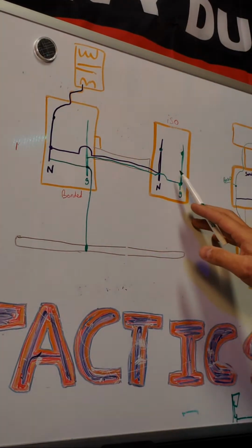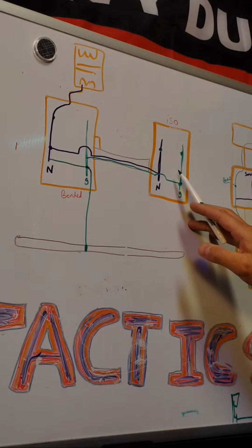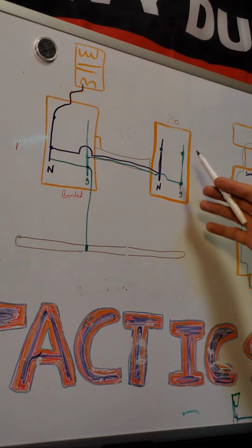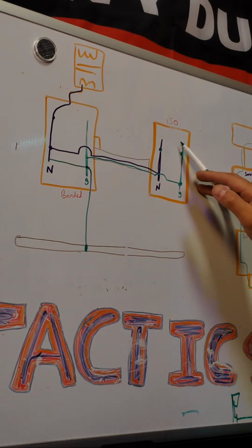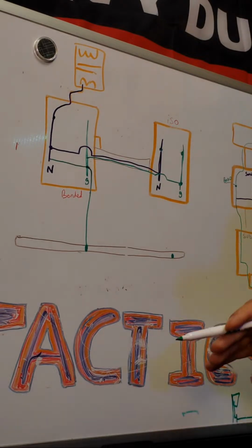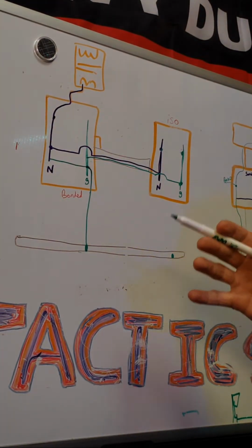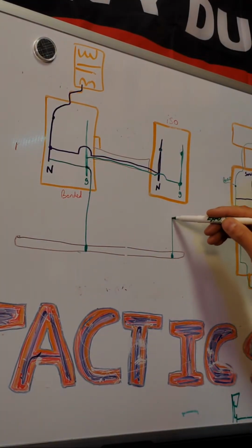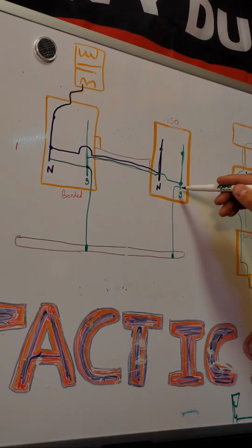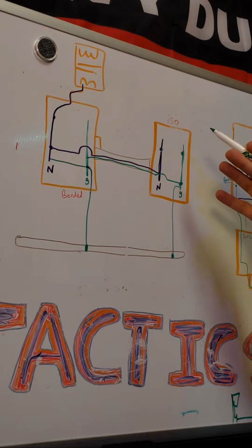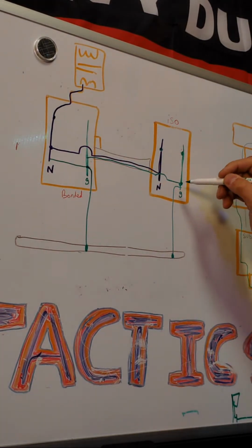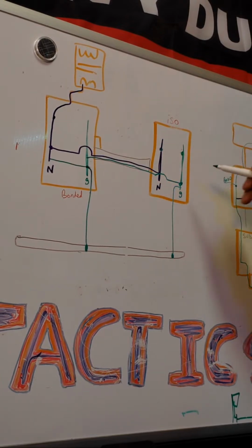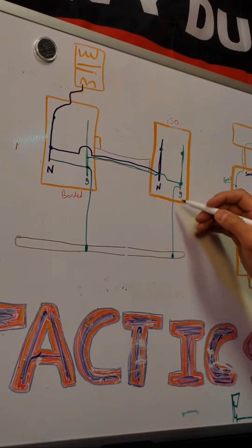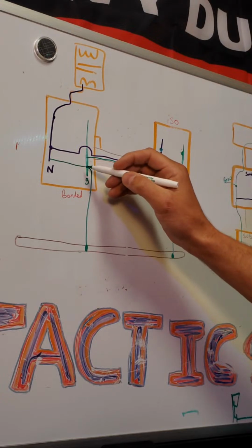So if this was an old sub panel in the closet and we happened to leave the old, right, because it used to be the service equipment, this is pretty common. So this panel here used to be the service panel, and it was in the closet. And we left that old number 6, which was no longer the proper size, but we thought to ourselves, hey, more grounding is better than less grounding. So we left it bonded. And we left that number 6 on this ground wire. We've unfortunately created a parallel path, and in the worst way too, because any current that was on the neutral is now going to be half on the ground, and we just introduced current to our pipe to get current back to the source.